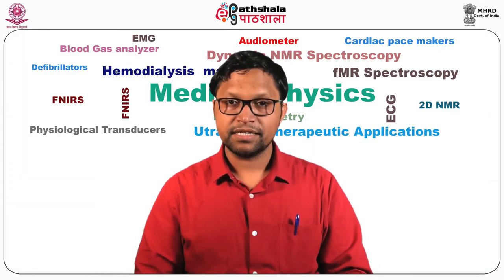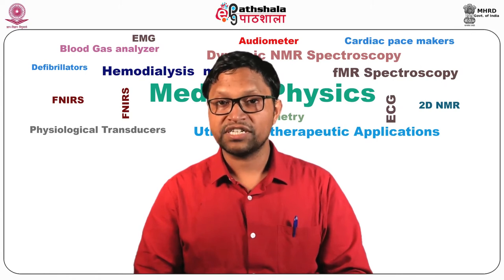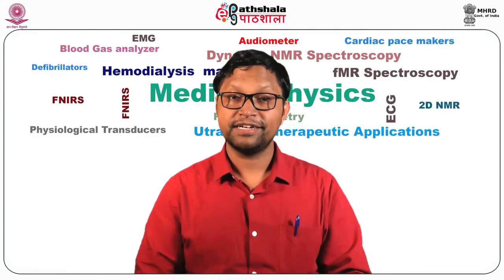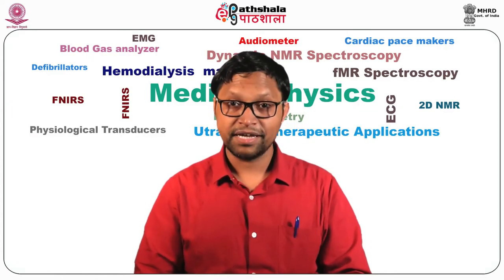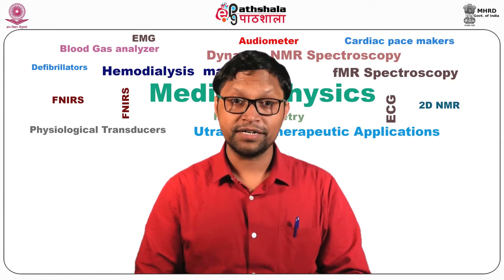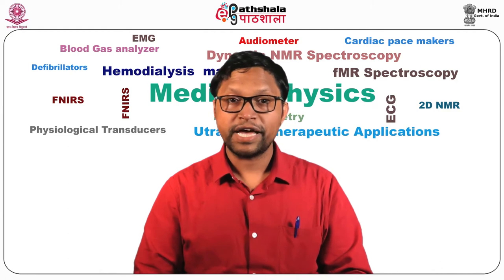We validated the BARC impedance plethysmograph equipment at our Autonomic and Vascular Function Lab in the Department of Physiology. A typical setup is shown for recording cardiac output monitoring in various physical conditions. The impedance plethysmography is a simple and versatile technique. It is also used to measure global or focal brain blood flow, which is called rheoencephalography. The electrode placement uses the 10-20 system of electrode placement.